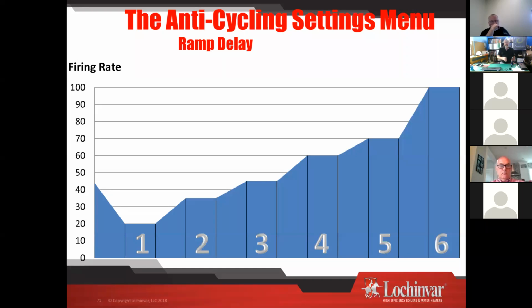So go back, we talked about cycling. We want to see no more than 6 cycles an hour in a fire tube design and no more than 10 cycles an hour in a water tube design. And that really gets into the water content of the 2 heat exchangers, why there's that difference. But if I want 6 cycles an hour, I want a 10-minute cycle. Whenever they put one of these boilers in, set those first 2 stages at 5 minutes apiece. Maybe you got a 5-minute stage with a 10% or a 15% firing rate. And then you go to your next one, another 5 minutes, bump it up another 5%, whether that becomes now 15 or 20%. You hold the boiler back, you allow it to take some time, you build in that automatic run, which is what the boiler wants. It wants to run. We're going to get some time where we're condensing.